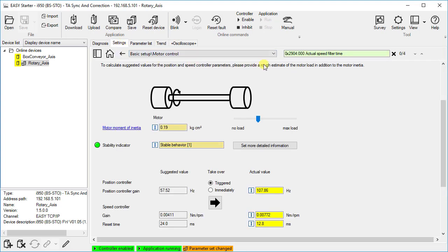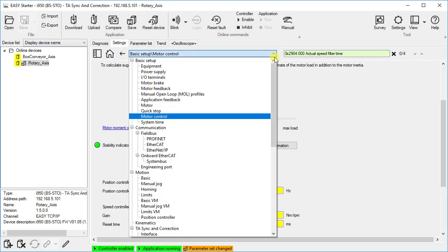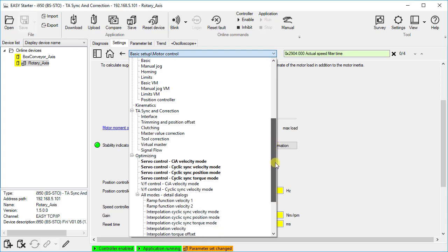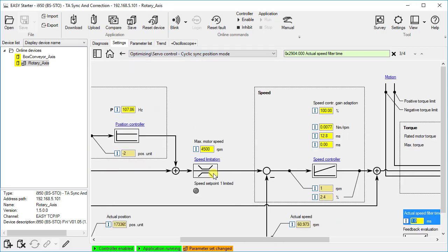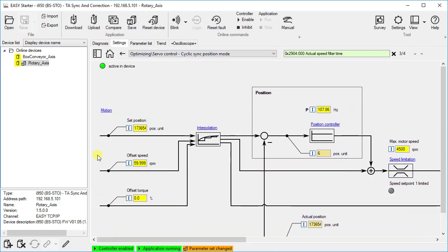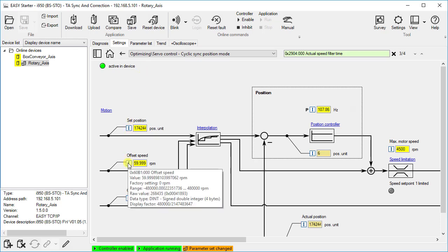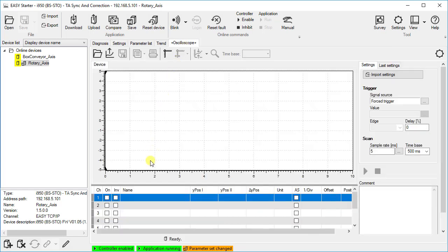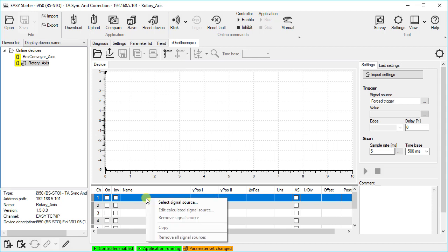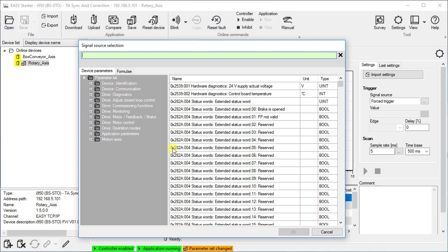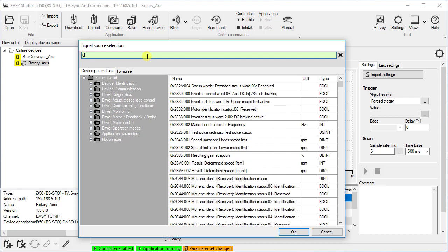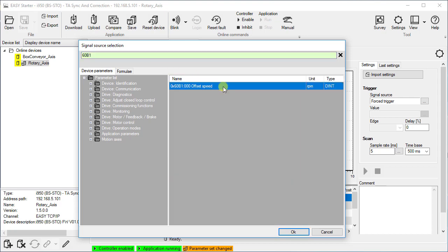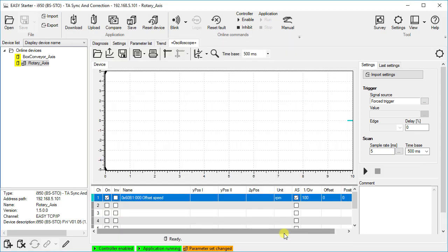We go into the signal flow and keep the relevant parameter numbers in mind. For example, we want to record the speed reference value at the input of the motor control, here called offset speed. We remember the parameter 0x60b1. Let us put the variable on the oscilloscope. Right mouse button for selection works alternatively to double-click. Press the OK button. This closes the dialog box, and the selection is accepted.